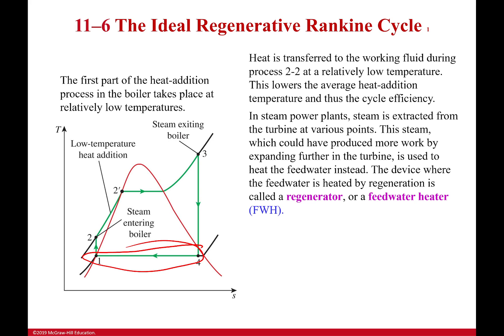In a steam power plant, things are very complex and we can have steam extracted at various points. If I extract it at different points it might not do work, but what I can do is use that steam to heat the water that I'll be heating using my boiler — so I can use this steam to preheat my water. This is a form of regeneration.